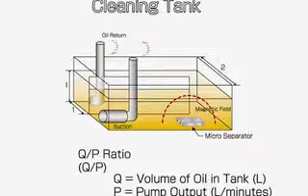The quantity of microseparators used in the cleaning tank system should be determined by considering conditions such as the structure and capacity of the tank, the QP ratio, pumping pressure, and type of oil used.